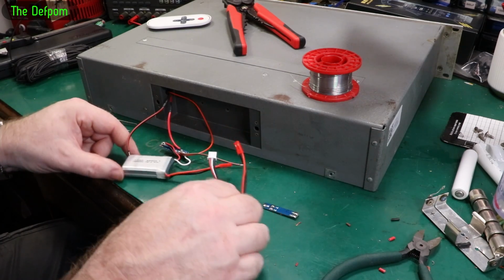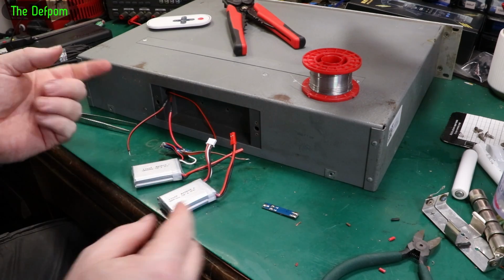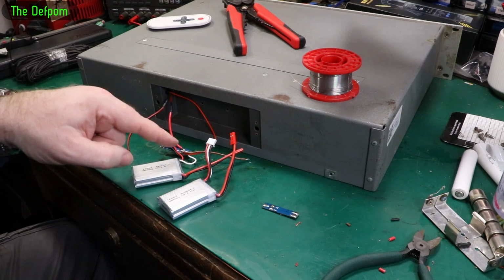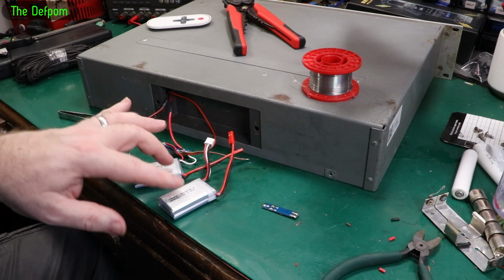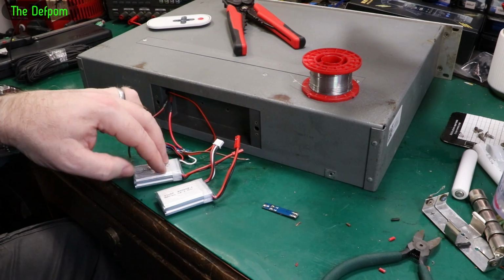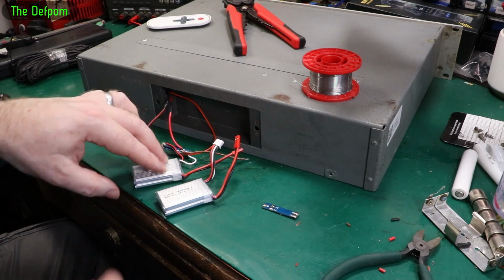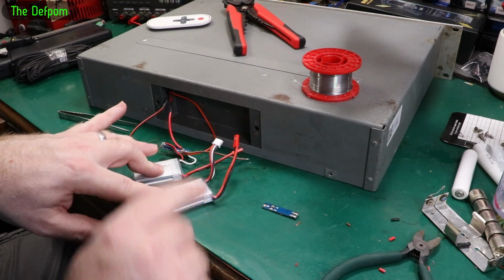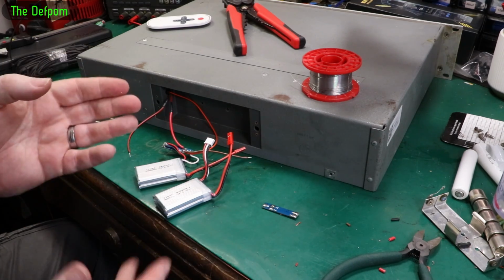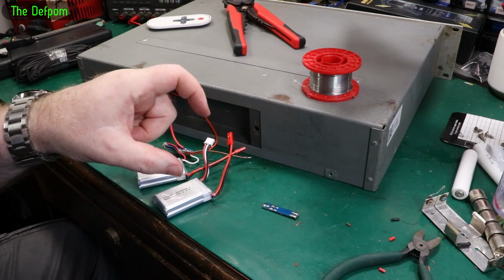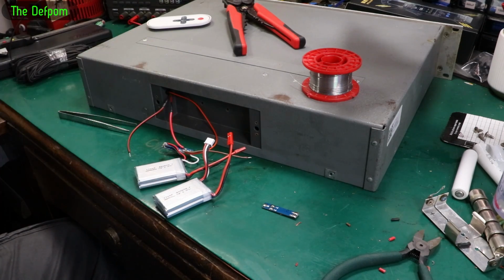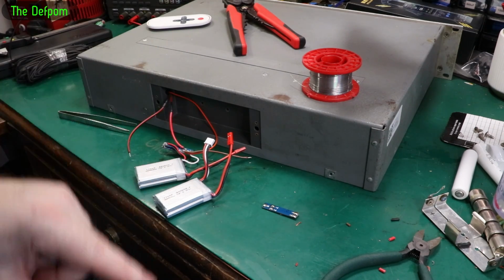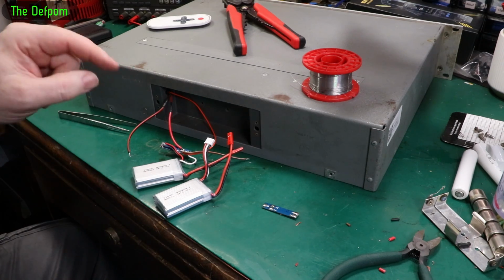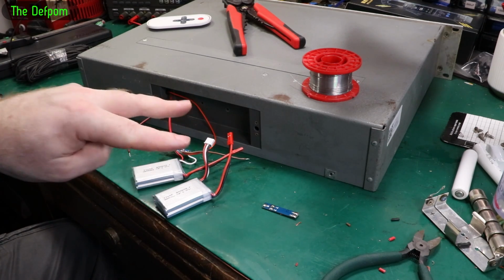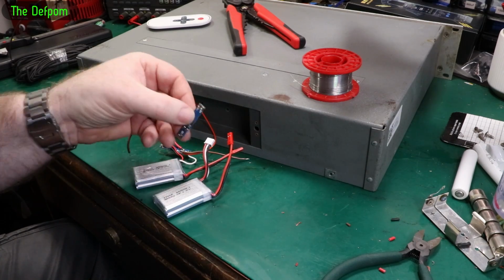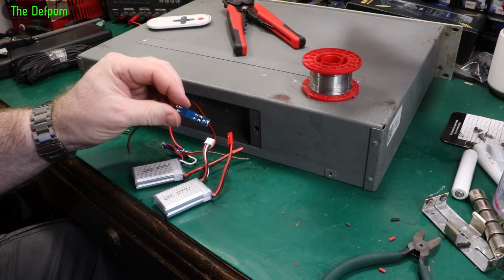So if I wired these up as a single pack, and because I'm using a battery middle connection in between those junctions, it'll only disconnect this battery. The positive side will still be connected, because it'll only disconnect the negative one, right? Because that's how those things work. They disconnect the negative side of the battery in order to control the charge rates and stuff like that. So thinking, well, if I use one of those, it wouldn't actually work correctly in this instance because it's got a battery middle connection. It's a split supply. So because of that, I have to use 2 individual battery protection modules.